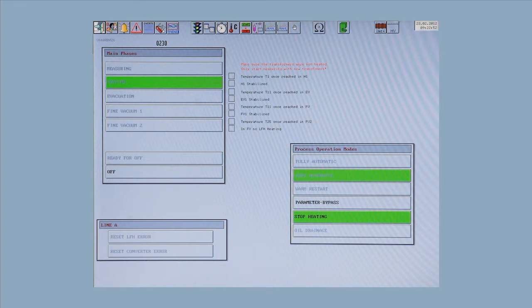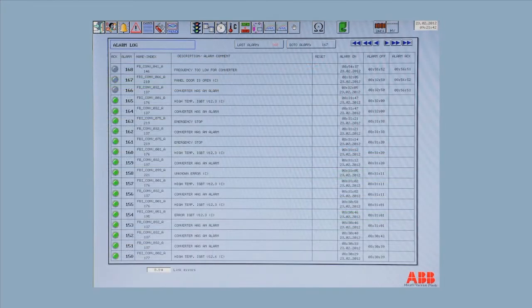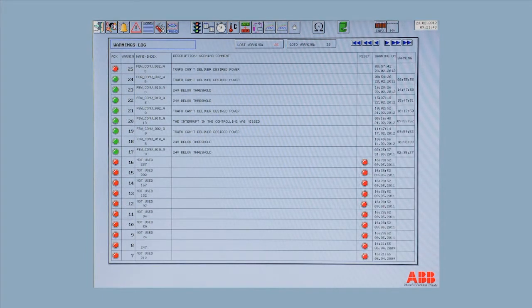The converter alarms must be reset in the phase control screen, while the alarms from the rest of the plant should be reset in the alarm screen. There is a similar screen for warnings. Most alarms do not need to be reset. When the situation that has created the alarm has been solved, the alarm is reset, but it still remains green, waiting for the acknowledgement from the operator. The process will go on in the meantime. Summary.